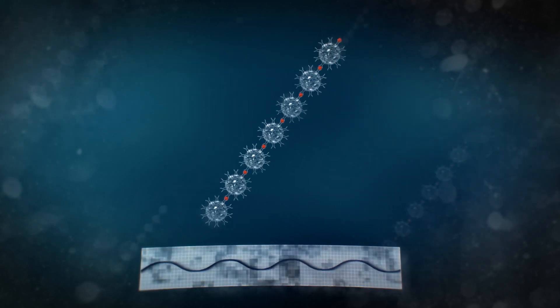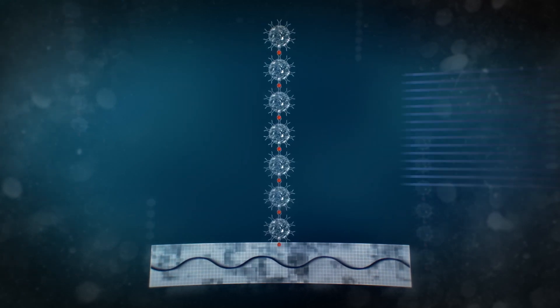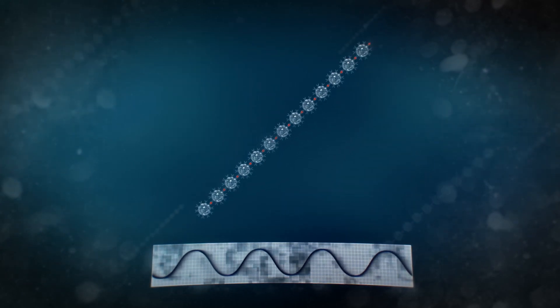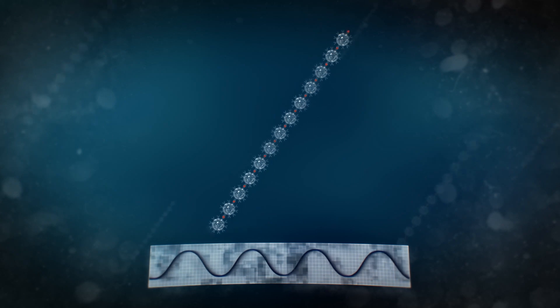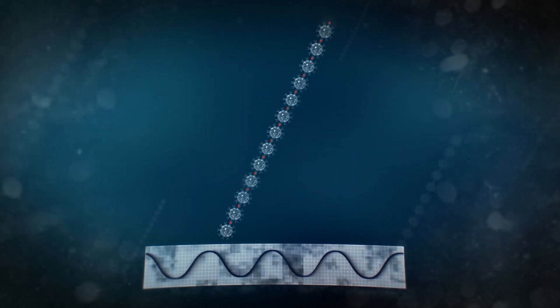If the rotating chains are bombarded with laser light, the intensity of the light penetrating them changes in time while rotating. This can be measured. The longer the chains are, and the more antigens there are in the blood, the more violently the laser light intensity will vary. If no disease molecules are present at all, the intensity of the light does not change. With our technology, not only can we determine with certainty that antigens are present, we can also establish their number by measuring the amount of light that is modulated by the rotation of the nano-chains.